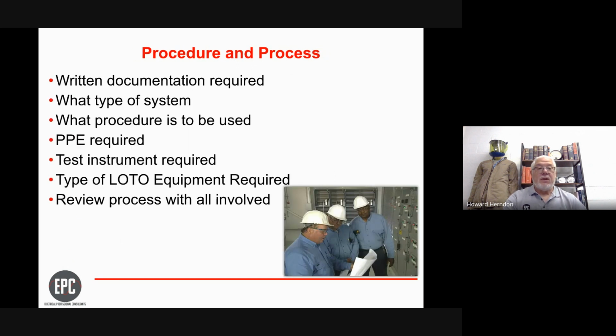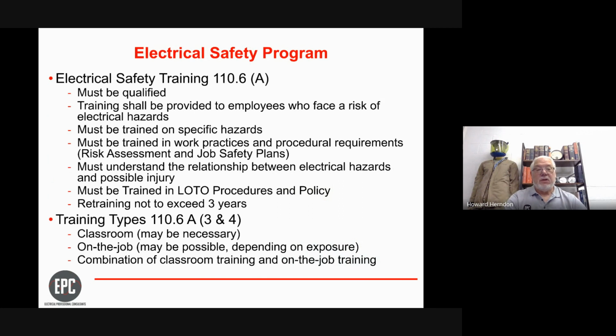Again, written documentation is required for procedures. Make sure we look at what kind of system, what kind of procedures will be used, what the PPE requirements are, what test instruments are required, and what the lockout tagout requirements are. There are a lot of different lockout tagout attachments, so we need to make sure we have the appropriate one for that device. Review the process with everyone.